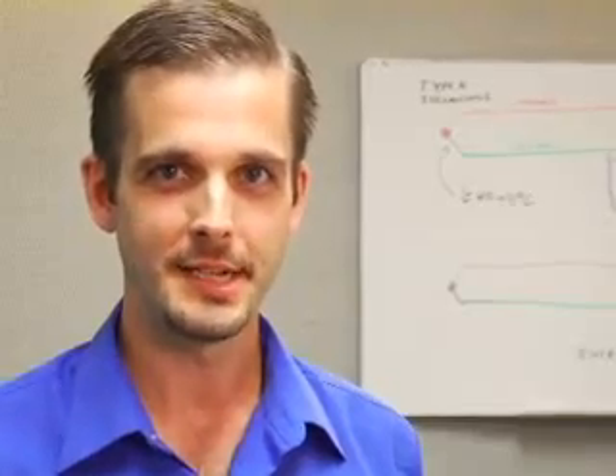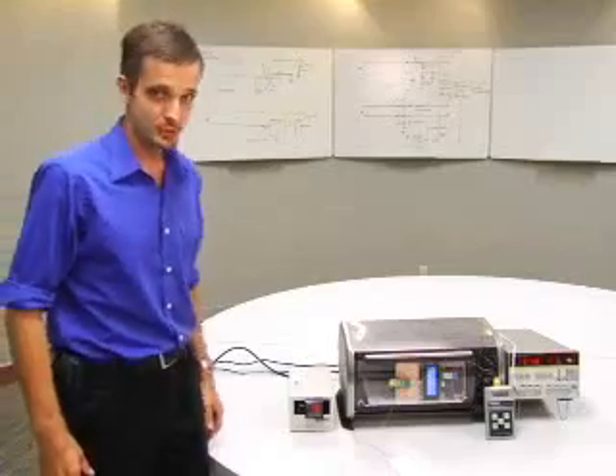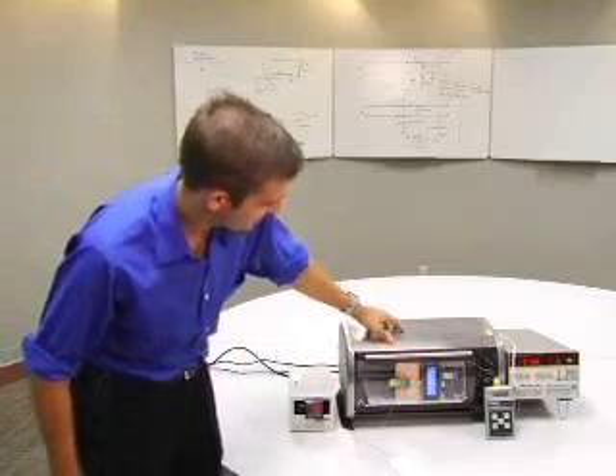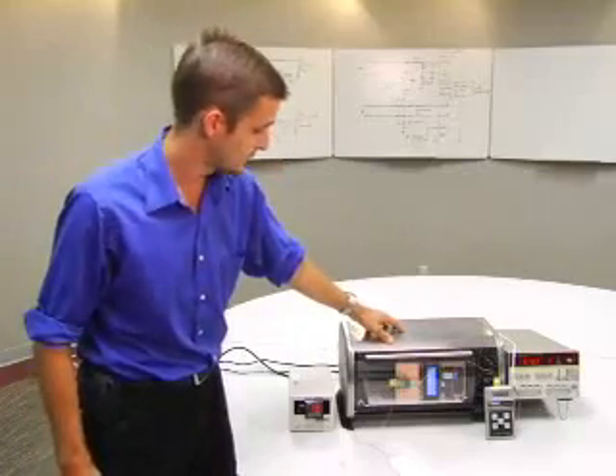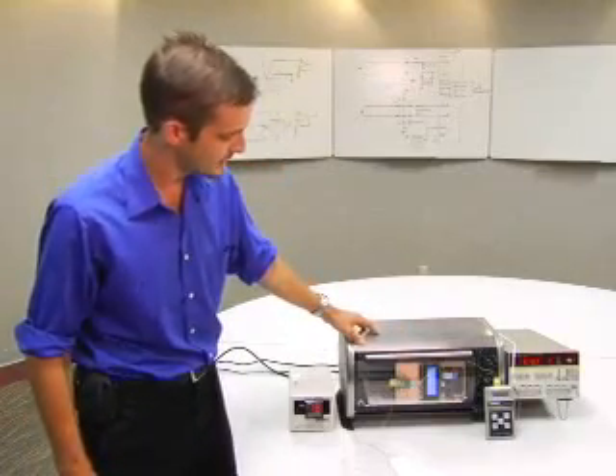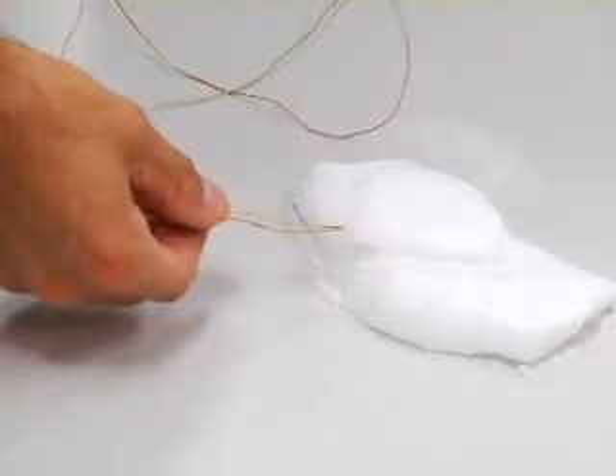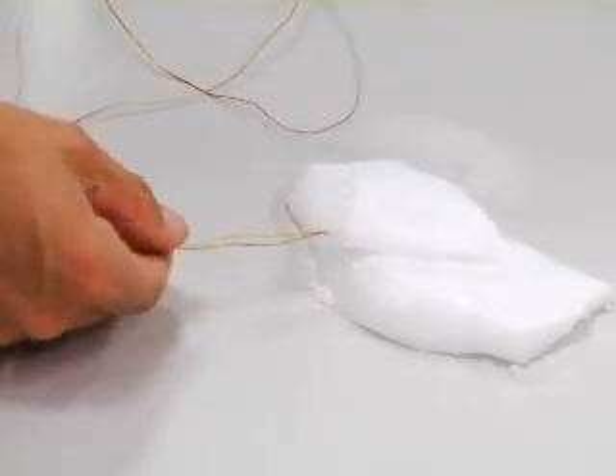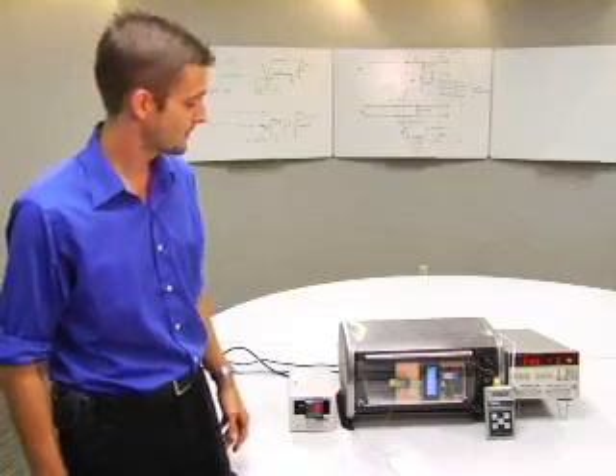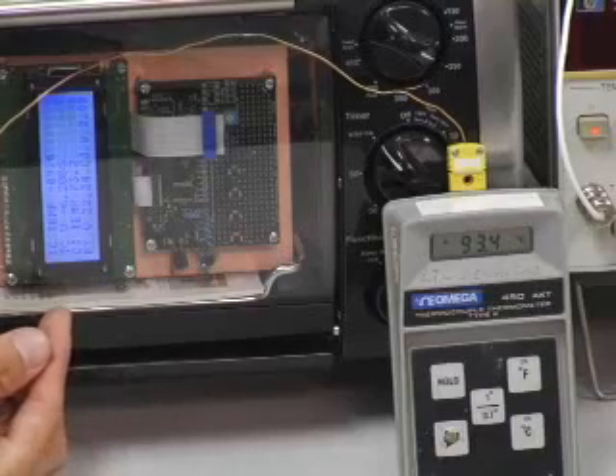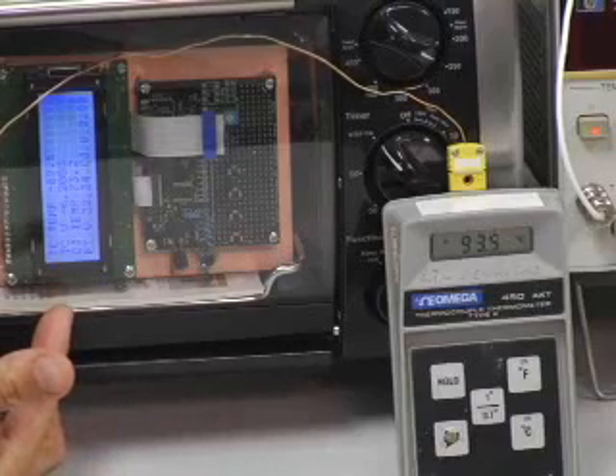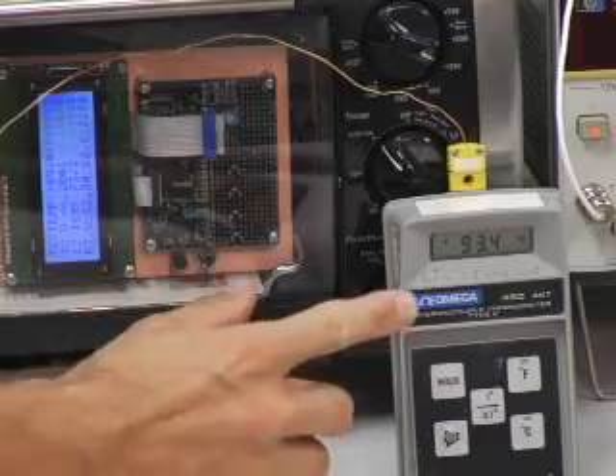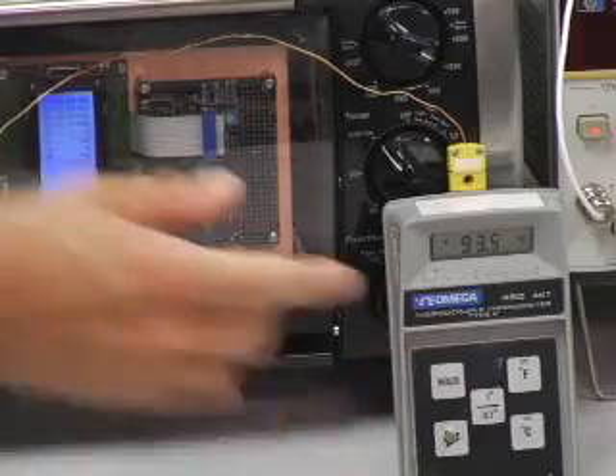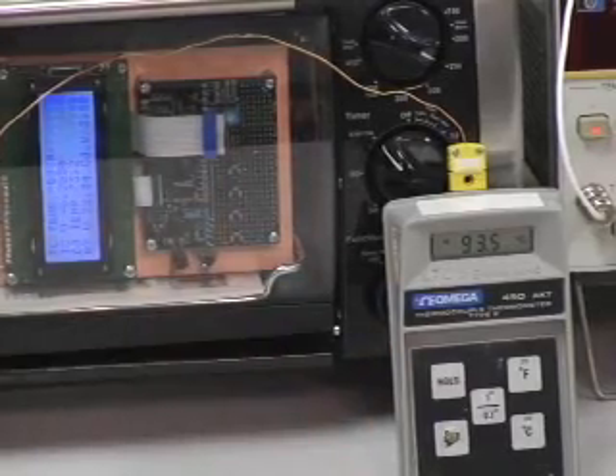It's also a good idea to test unexpected situations. So here we've got the case where the thermocouple meter, or the so-called cold junction, is in an oven at 75 degrees centigrade, and the thermocouple is in a block of dry ice. So that's a way to test out how good your cold junction compensation is. So here you can see the thermocouple temperature is at about minus 89 degrees centigrade, and this meter is reading about minus 93 or so, so we have a little bit of discrepancy.